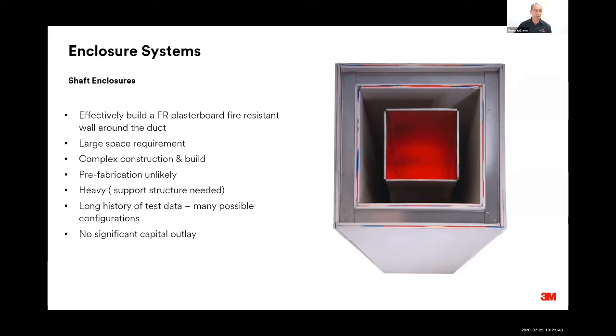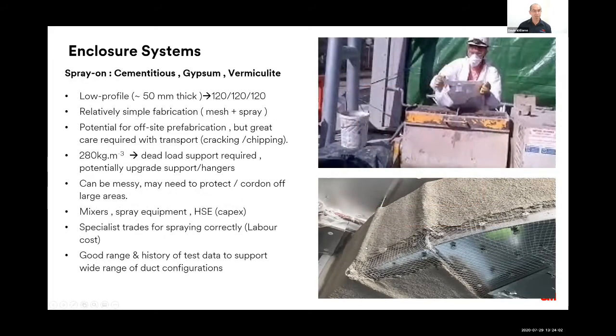It can be heavy, so you might need to incorporate more support for the duct, but there's a long history of test data for a lot of configurations for plasterboard fire-rated partitions, and generally not a large, significant capital outlay for building these sorts of structures. Secondly, we have spray-on systems. Generally, they're a much lower profile, at 50 millimetres thick for a 2-hour fire resistance rating.